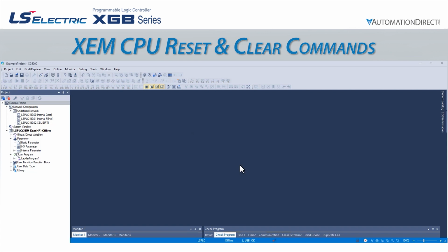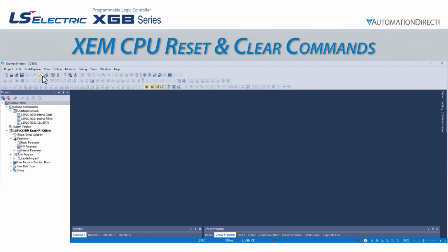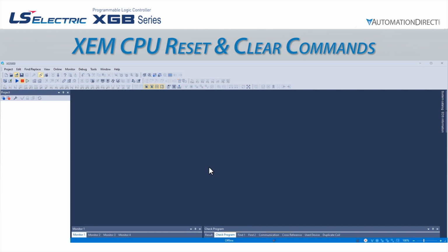It is very important to note that once we have performed this clear all, the only supported way to connect to the PLC again is using the USB cable initially. The Ethernet connection will not work until after we have rewritten a valid IP address to the CPU using the USB connection. Also, it will not be possible to read a project from the CPU since no project is present.